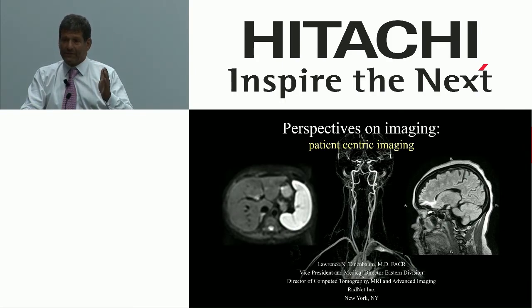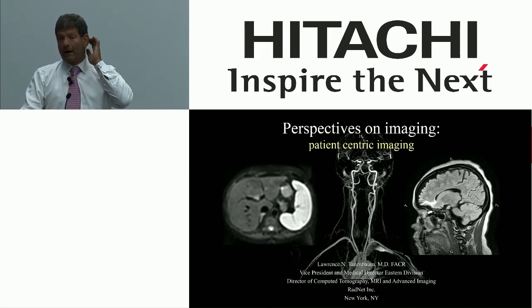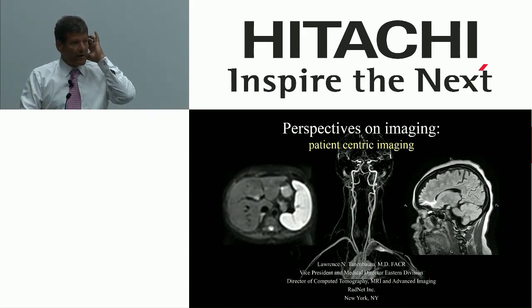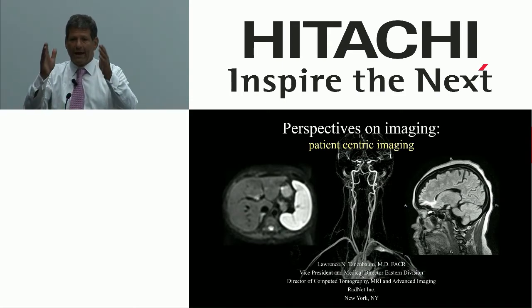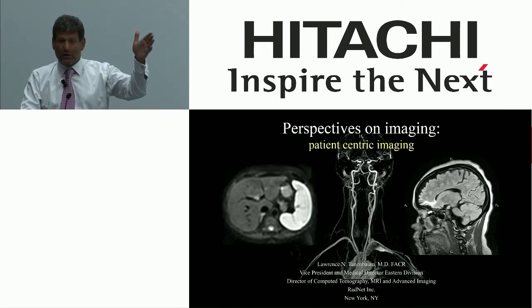As a matter of fact, thank you for bringing that up, if you ask me and you're not using these, and by the way, you're probably not, I would suggest that the best way for you to spruce up your quality and your efficiency is to get to using these right away. I use them on every single thing. I walk into an old machine, I may be doing that today. As a matter of fact, I fully expect to be there today, with unhappy doctors about image quality, because things have drifted downward, and sometimes all I have to do is go in and apply the appropriate noise reduction.